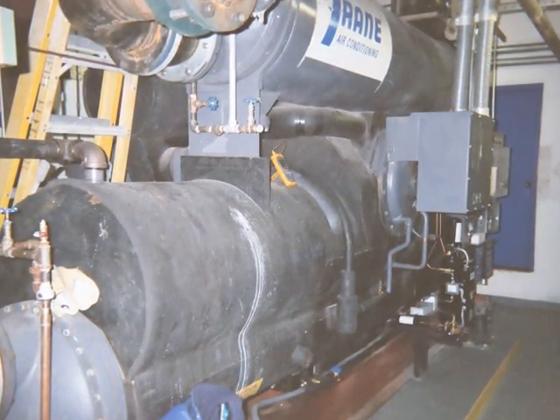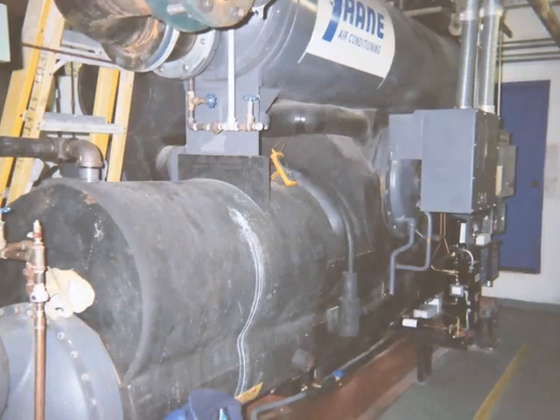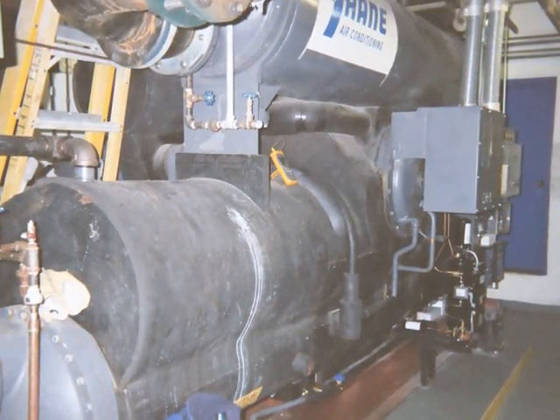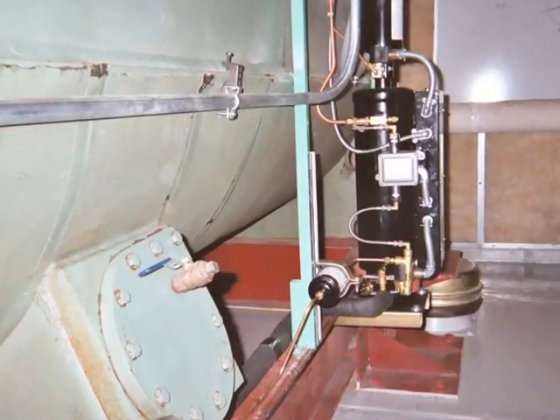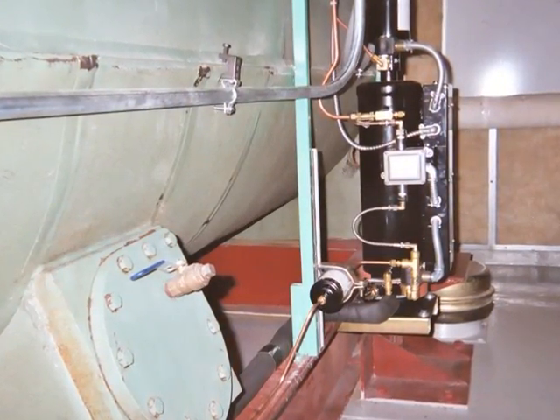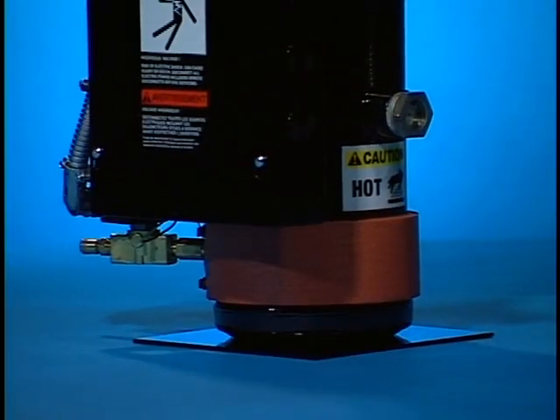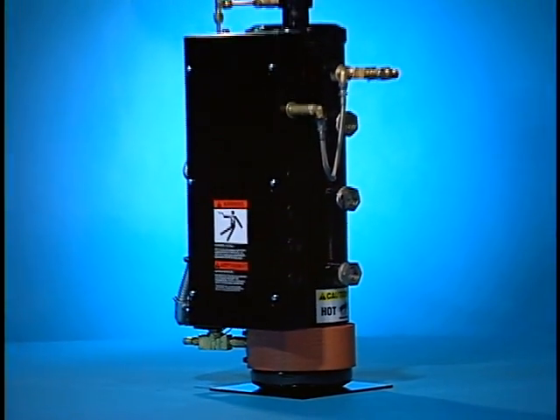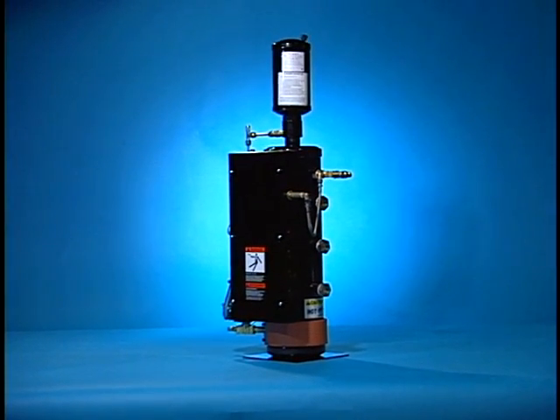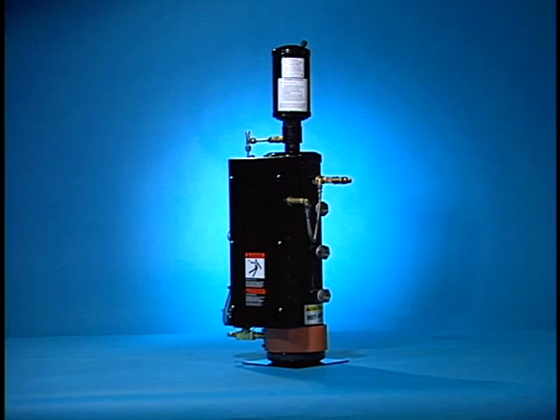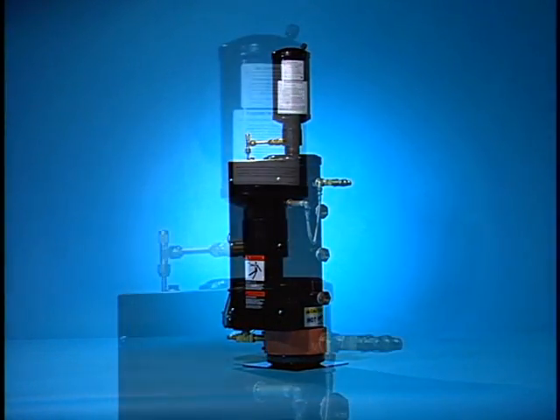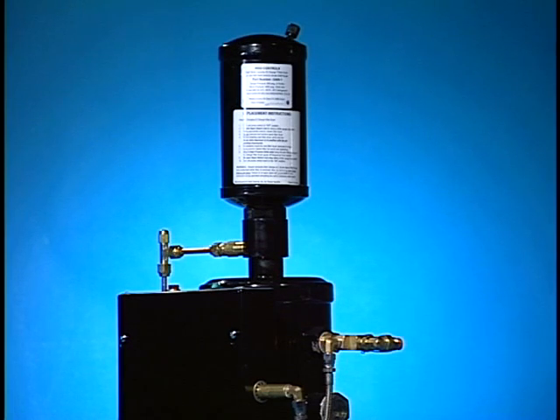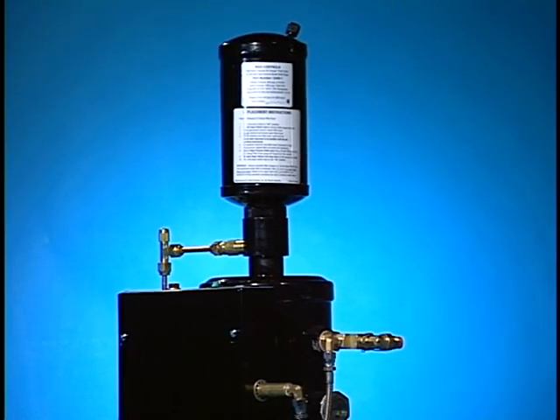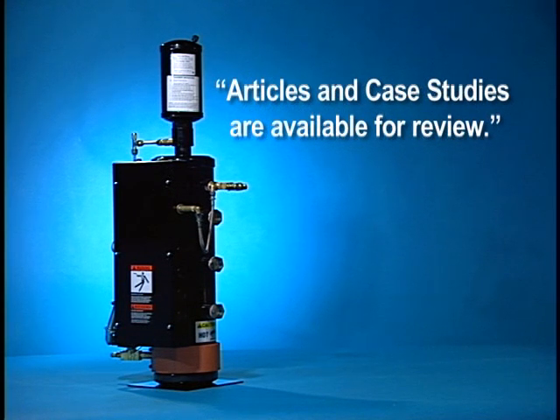The extra oil is causing excess energy to be used, and anytime we use excess energy, that causes more global warming gases to be put into the atmosphere, and clearly today's primary threat from an environmental standpoint is climate change. The bottom line is this: there is no chiller that cannot benefit from an OAM Purger. You will save thousands of dollars, not just the first year, but every year you operate the chiller with an OAM Purger, forever. Not only will the OAM Purger save you thousands of dollars in energy cost, it also restores lost capacity. In addition, the OAM Purger helps reduce maintenance and prolong chiller life and refrigerant and oil life by removing harmful moisture and acids from the system.